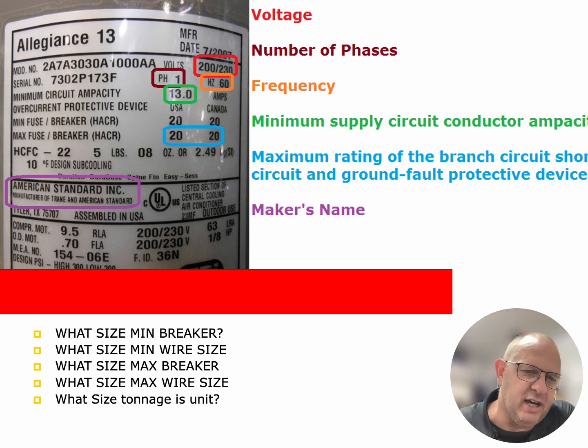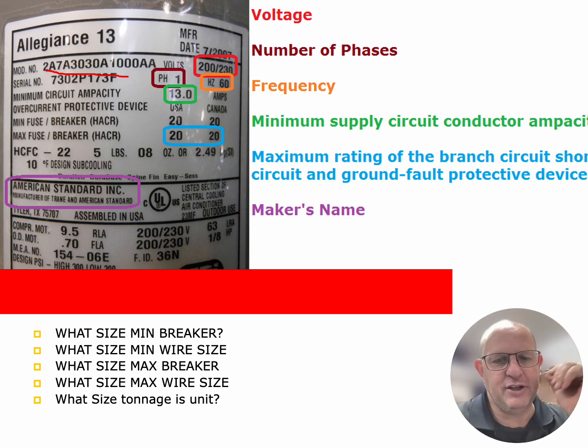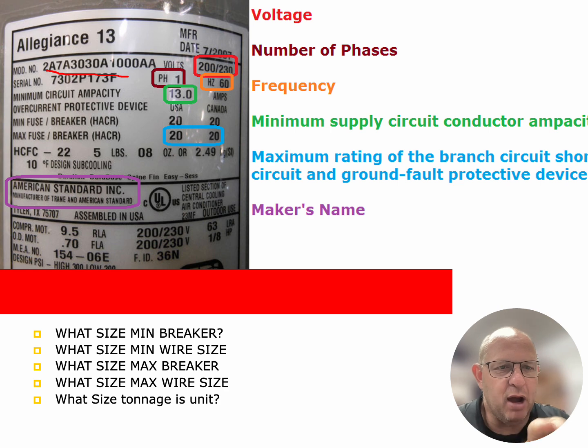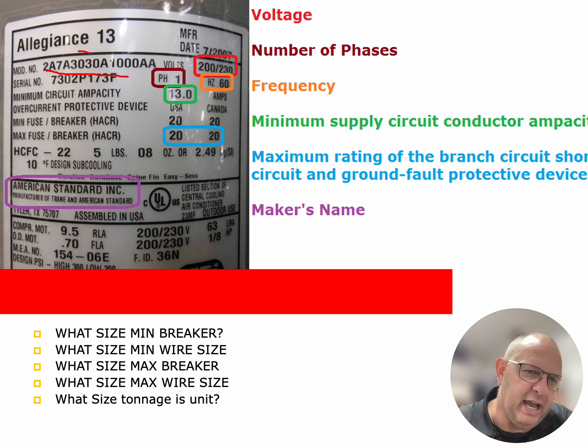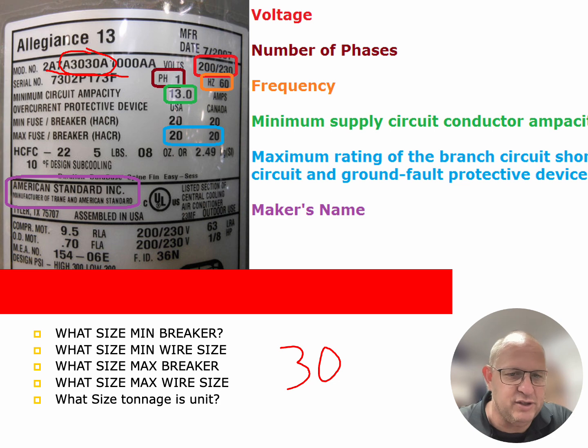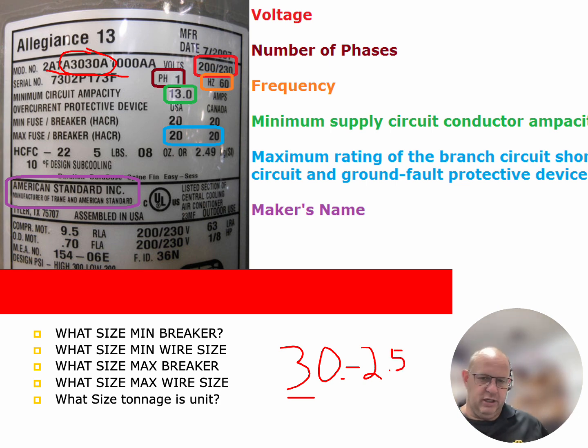Okay, next question. What size tonnage is this unit? I'm going to check the model number. Got 2A7A 3030A. There's my model number. Without looking at the breakdown of this particular unit, your guess is as good as mine, but we can make a good educated guess right here and know that we're probably dealing with a 2.5 ton. Now I'm going to be looking at these two numbers here. I don't know the breakdown of this particular model, but I know that I have two numbers that could actually be the tonnage of the unit. So 30 would equal out to be a 2.5 ton unit when I'm looking at the refrigeration that's on this particular unit itself.